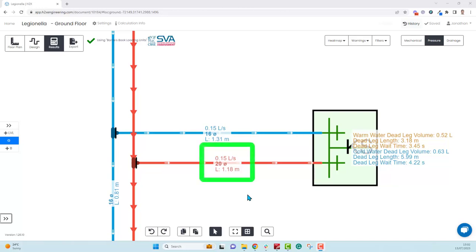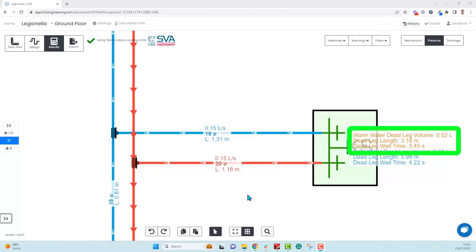There are three parts to a dead leg calculation. You have the flow rate, which is governed by the fixture, so it's not really within your control. You then have the pipe diameter - the larger the pipe, the more volume of water is in the dead leg, so you want to keep the pipe size to a minimum as much as possible. There's also the length, which you want to minimize too. These three things combined give you your dead leg volume - that's the internal pipe diameter multiplied by the length. If you divide that volume by the flow rate, you'll get your wait time.